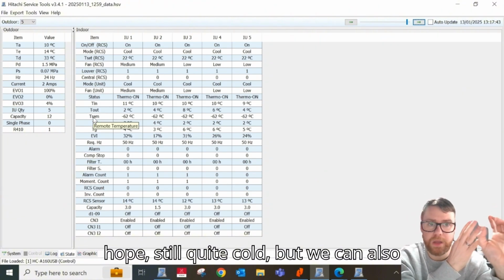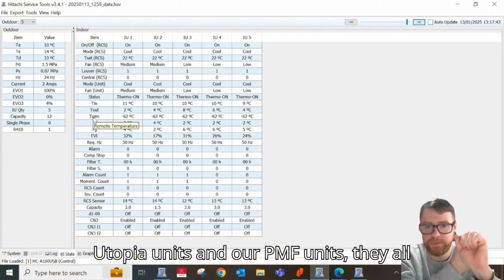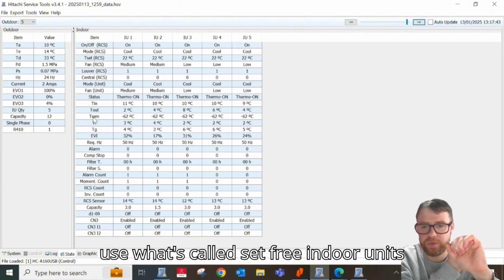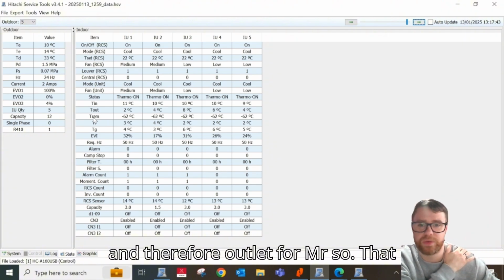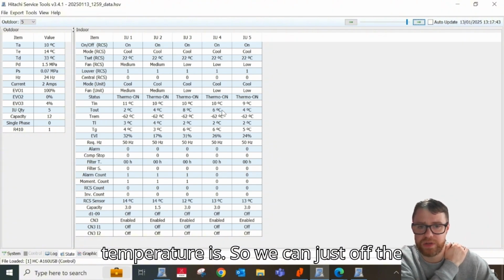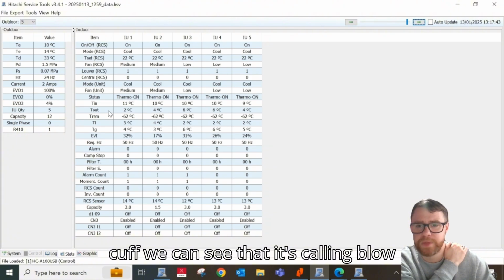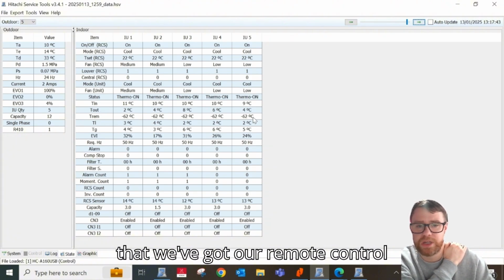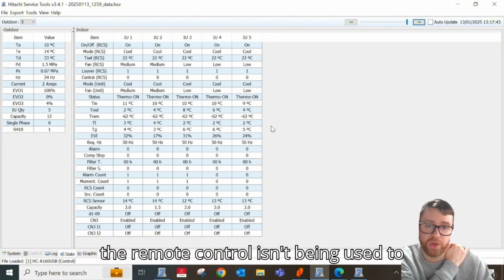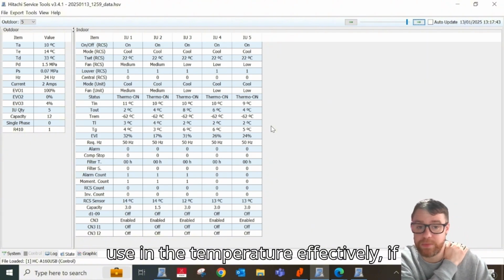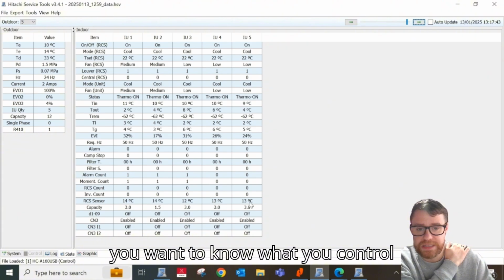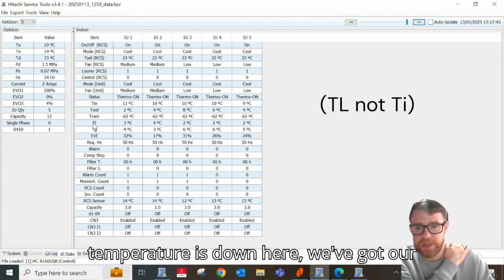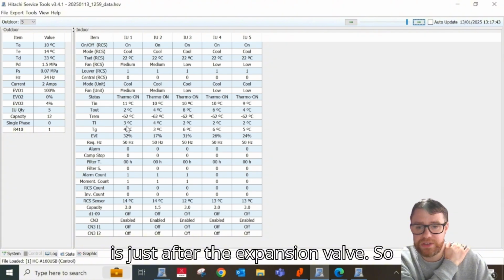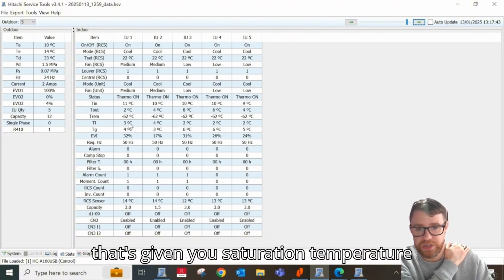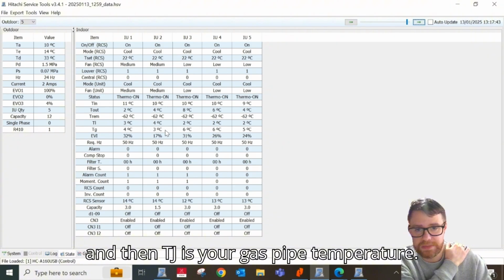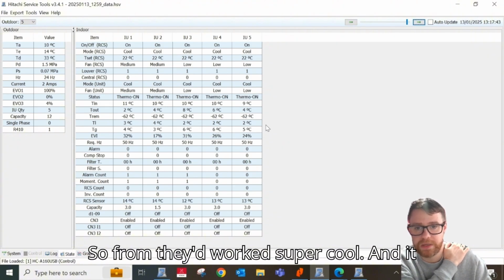On Hitachi Utopia units and our VRF units, they all use what's called set-free indoor units, and they have an outlet thermistor, so we can actually see what the unit's outlet temperature is. Just off the cuff, we can see that it's cooling. Below that, we've got our remote control temperature. That won't display if the remote control isn't being used for inlet temperature. If you want to know what your control temperature is, down here we've got our TI and TG. TI is your liquid temperature, just after the expansion valve, so that's giving you your saturation temperature, and then TG is your gas pipe temperature. From there you'd work out your superheat and subcooling depending on what mode it's in.